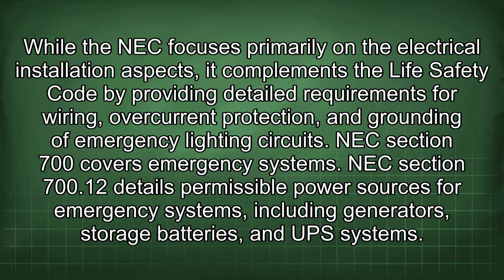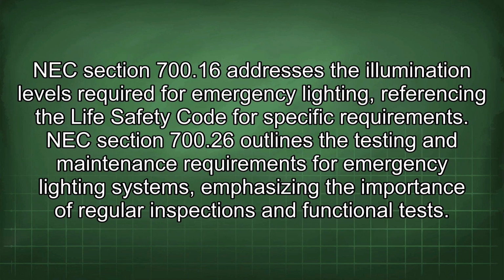NEC Section 700 covers emergency systems. NEC Section 700.12 details permissible power sources for emergency systems, including generators, storage batteries, and UPS systems. NEC Section 700.16 addresses the illumination levels required for emergency lighting, referencing the Life Safety Code for specific requirements. NEC Section 700.26 outlines the testing and maintenance requirements for emergency lighting systems, emphasizing the importance of regular inspections and functional tests.